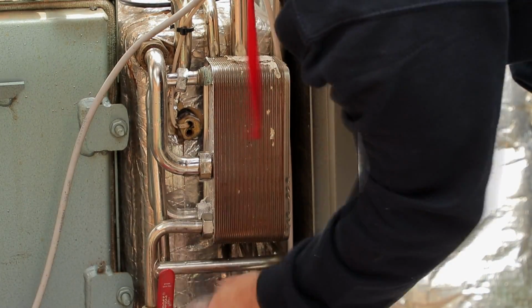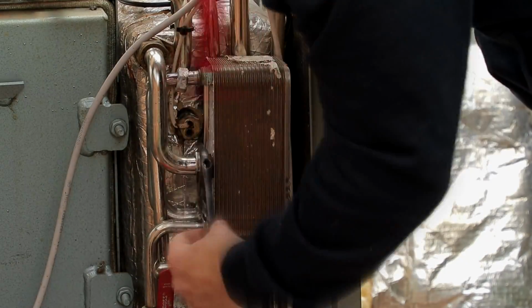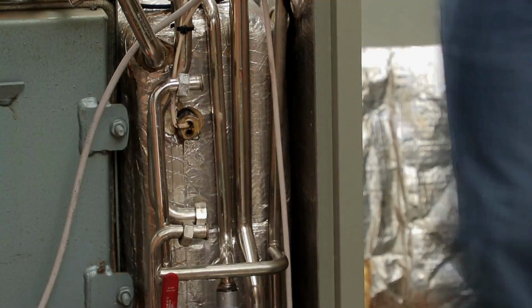Then I'll go into the house and open up every hot tap in the house, top and bottom if you've got a two or three story house. That makes sure that when we slacken off our hot out and cold nuts, we don't have a whole house's worth of hot water on top of us to come out. Basically what we're doing is getting it so we control the situation.